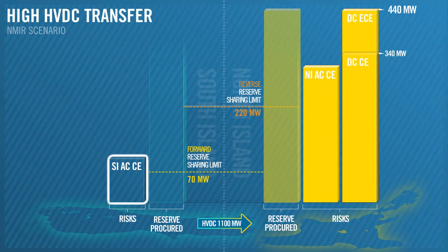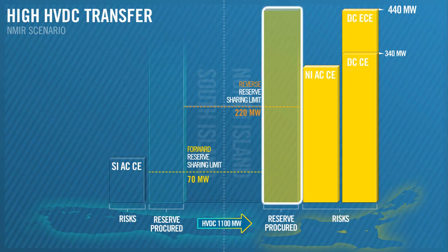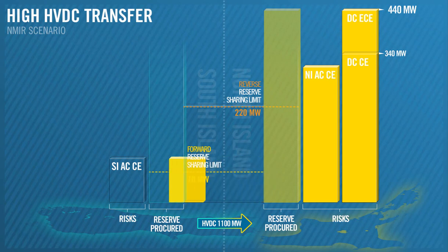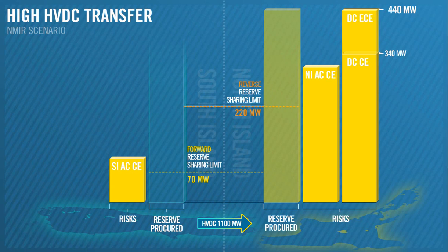Let's look at the South Island. We have already procured 440 megawatts of FUR from the North Island, 220 megawatts of which can be shared to the South Island. This is enough to cover the 100 megawatts of FUR required, even accounting for losses and the effectiveness factor. Therefore, no FUR is procured in the South Island.